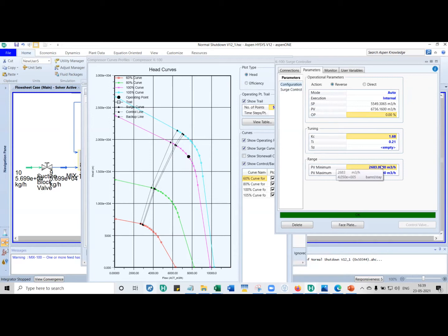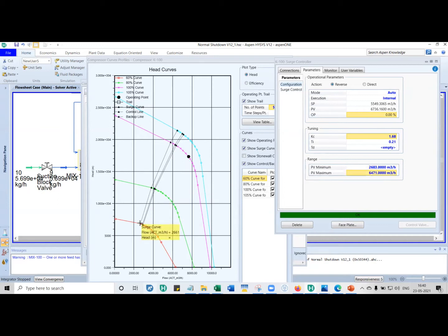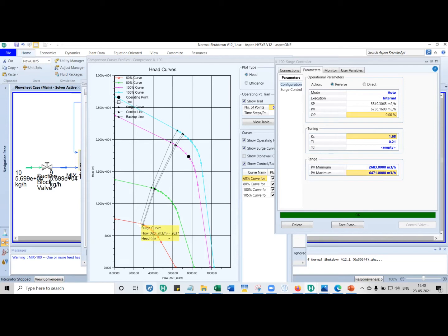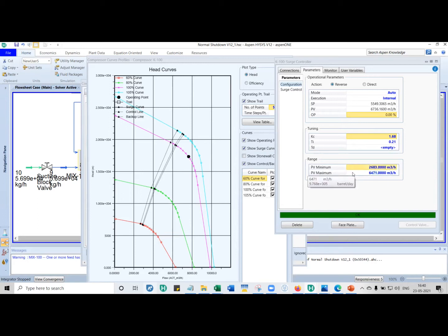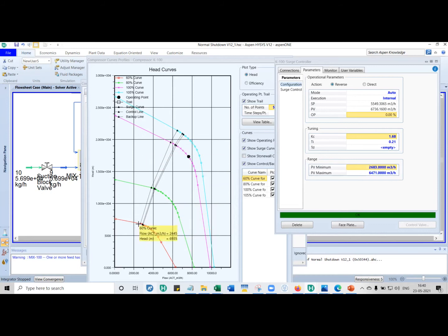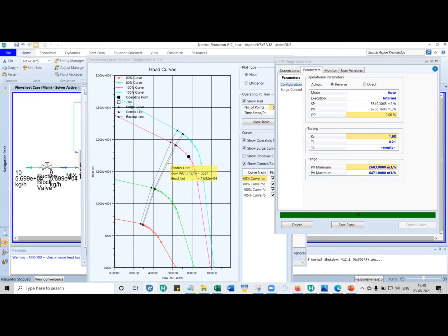Now, for controller parameters, PV max and PV min. The minimum amount of flow that can flow inside is for the lowest speed, left-hand side curve, so it is about 2,637, whereas the highest on this end is about 9,118. This PV min and PV max is not the surge lines. It is this number, from here to here, so it will be 9,000 something that you have to enter.